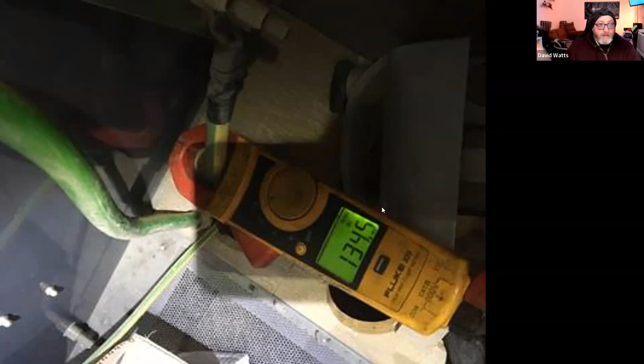I would put a clamp meter on, see there's nothing there, bridge, disconnect, and maintain work. Because at any time, someone up the road can come in and turn the oven on whilst I'm working, so it could be measured that there's nothing there. Then 20 minutes into my board change, loads of amps can start to appear, and I would not know that. So I need to have a constant control. We can't think of it as being dead.